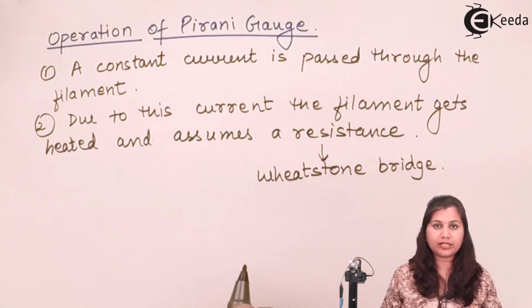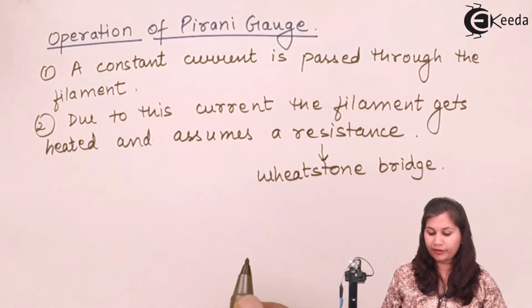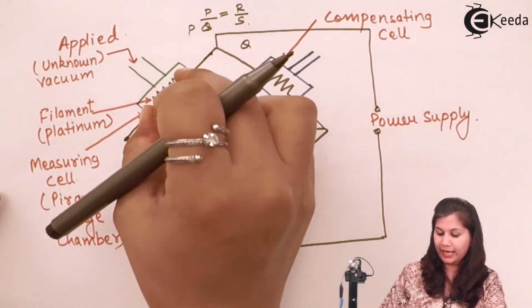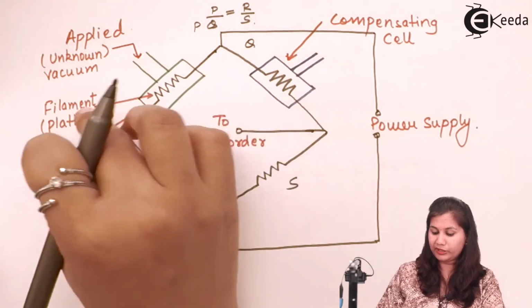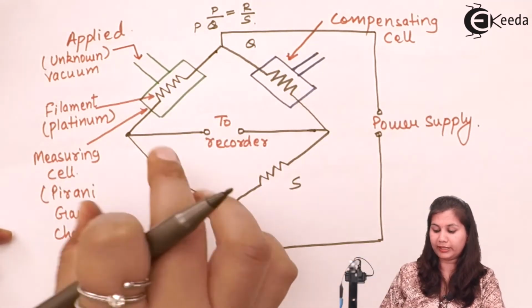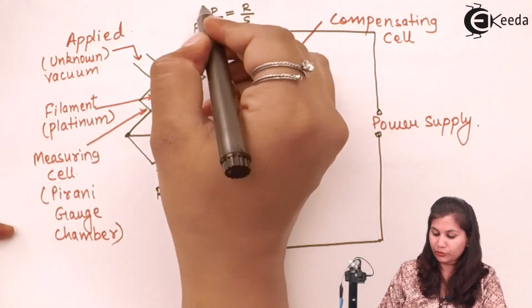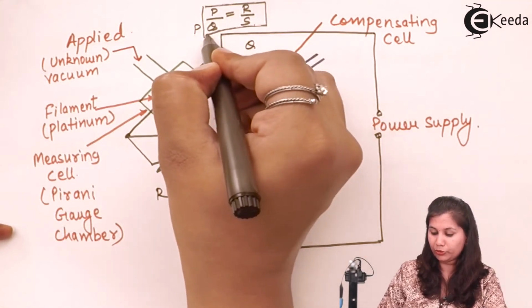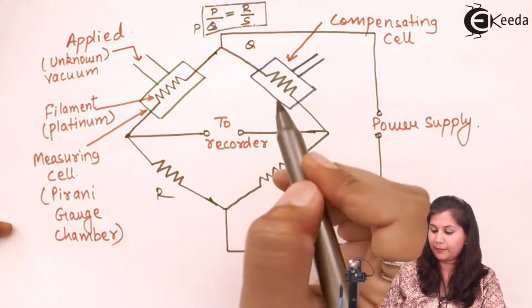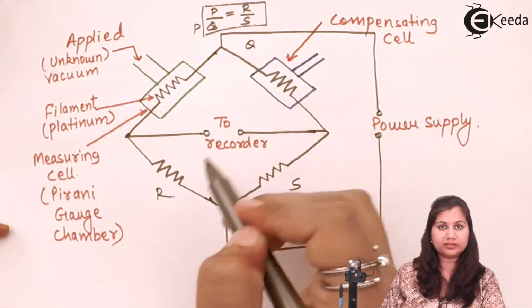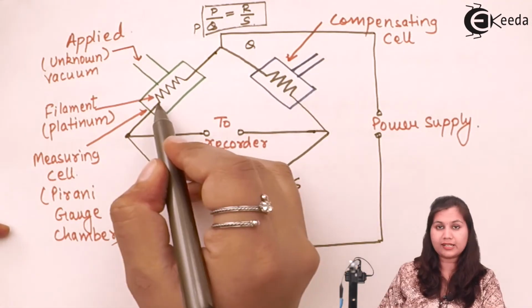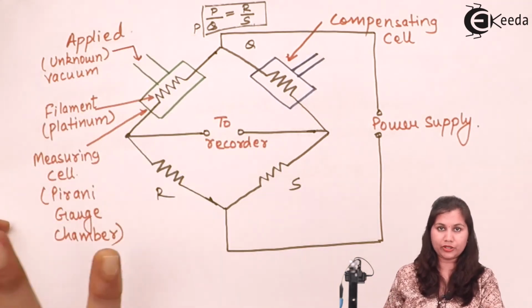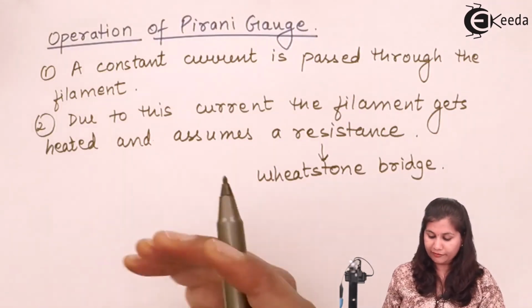So at the first stage, the filament is connected, and we are passing a constant current through this filament. This filament will act as a resistance, and this resistance is measured with the help of the Wheatstone bridge by using this formula P upon Q is equal to R by S. Because we know the value of all the other three resistances, and this is the unknown resistance, we can measure its value.